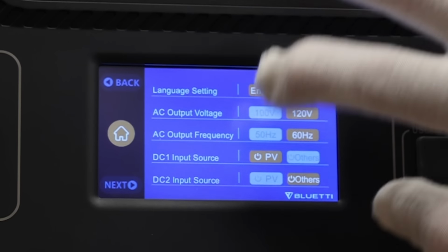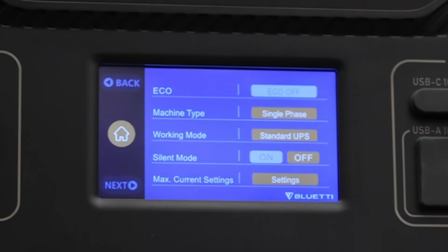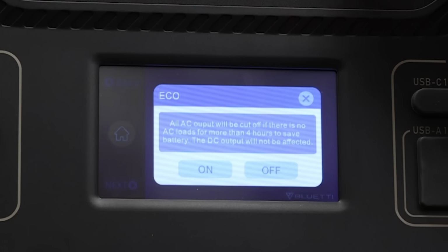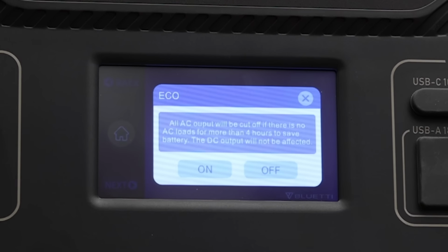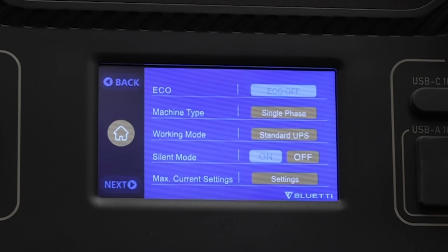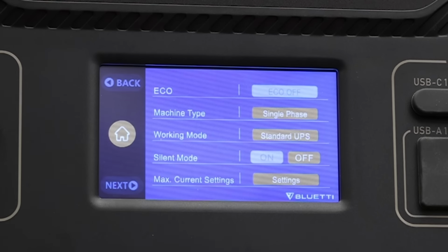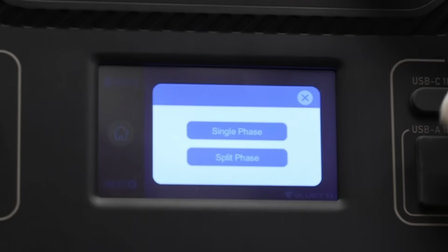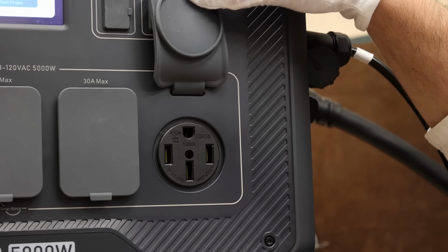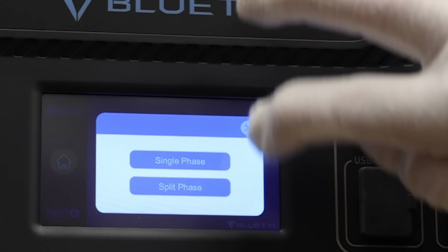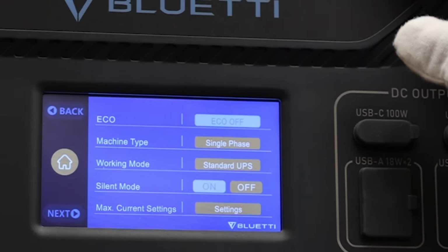PV will allow you to charge at a higher voltage. Click next: Eco mode will actually turn off AC loads after 4 hours — I recommend leaving that off unless you really need it. Machine type: single or split phase. If you want to use the 50 amp RV output, you need two of these units and put them in split phase to get 240 volts.